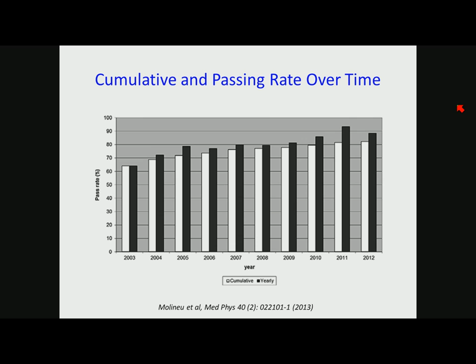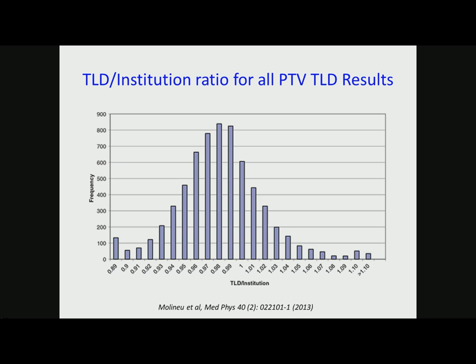Usually, they're on the cooler side. So the TLD divided by the institution. So the TLD is lower than what the institution is claiming, the treatment planning system it is. So this is 1 right here, and it's kind of about 2%. That's where the peak of this curve is. And as you can see, there are some institutions that are 10% off on either side, and that's not a good thing. I mean, they're treating patients with this. So how accurate is their treatment planning system being commissioned?